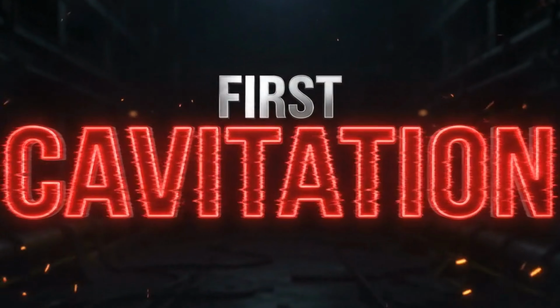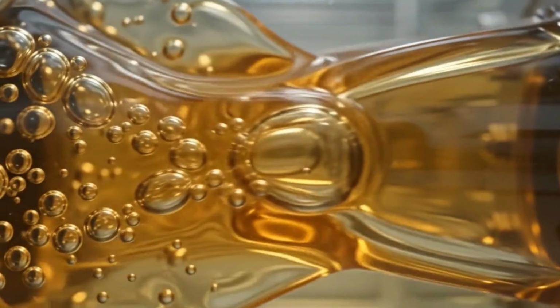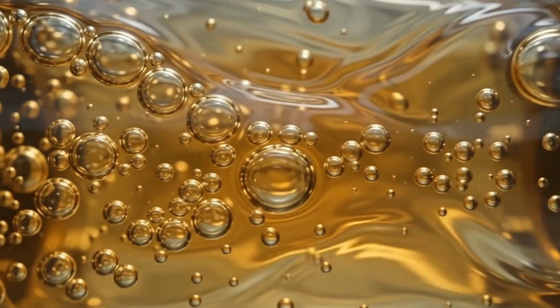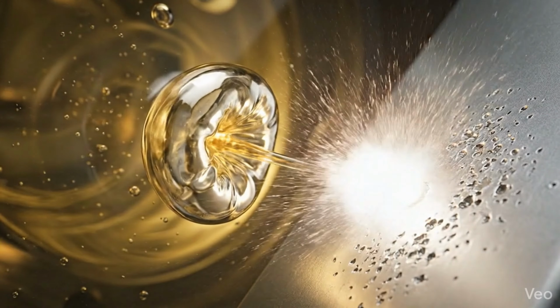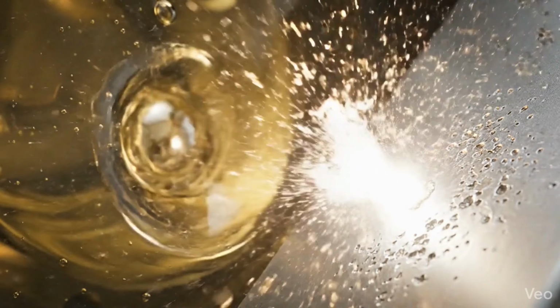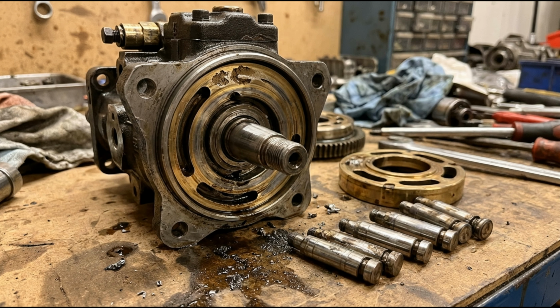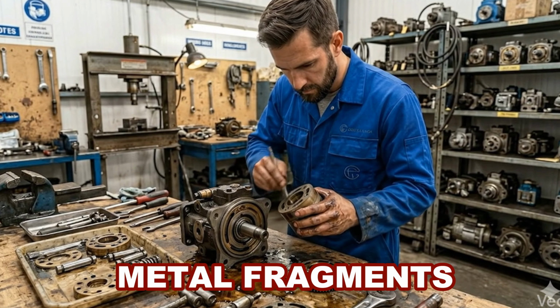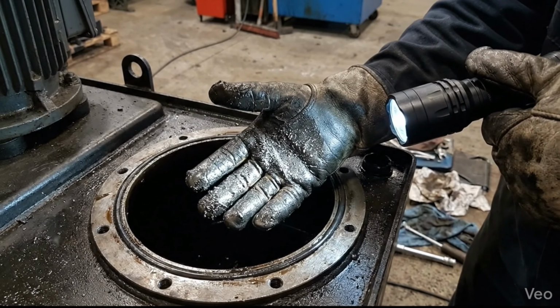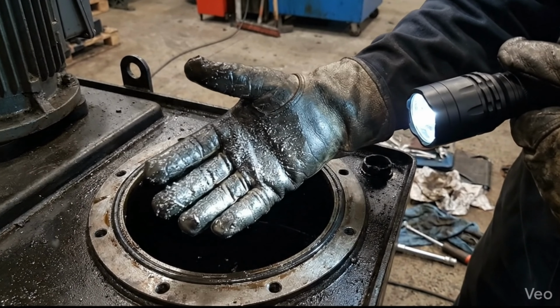First, cavitation. The vacuum causes millions of oil bubbles to form and aggressively implode inside the pump. This violent action tears away metal fragments from the pump housing, scattering them throughout your entire system.